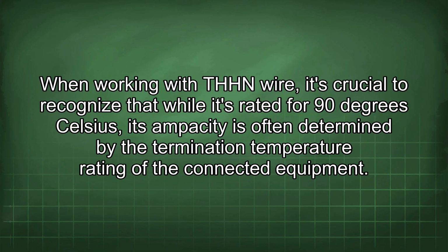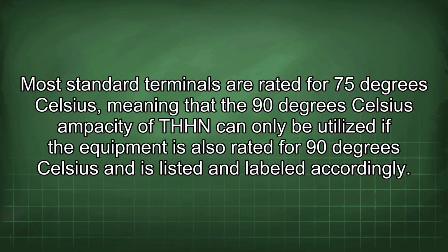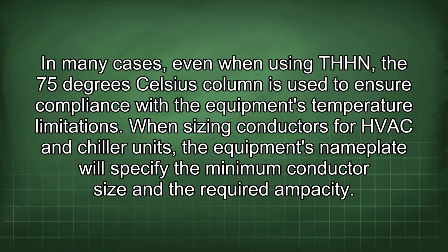When working with THHN wire, it's crucial to recognize that while it's rated for 90 degrees Celsius, its ampacity is often determined by the termination temperature rating of the connected equipment. Most standard terminals are rated for 75 degrees Celsius, meaning that the 90 degrees Celsius ampacity of THHN can only be utilized if the equipment is also rated for 90 degrees Celsius and is listed and labeled accordingly. In many cases, even when using THHN, the 75 degrees Celsius column is used to ensure compliance with the equipment's temperature limitations.